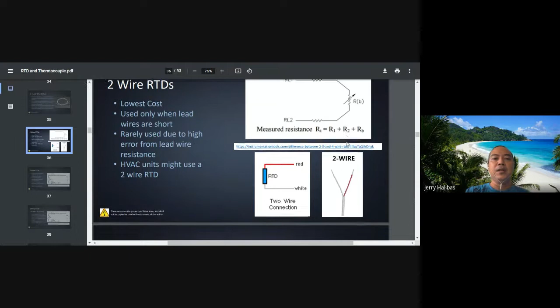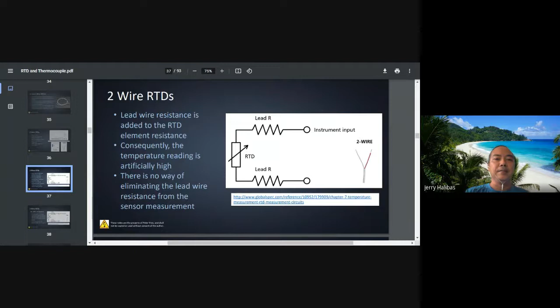Your reading will change. That's why you can still represent the circuit this way. So your lead wires or extension wire or instrumentation wire has an effect. Usually you use instrumentation wire because it's a braided type, similar to UTP or STP, shielded twisted pair, with braided shielding, even foil, but it's stranded because it's meant to bend, not solid. Unlike other twisted pairs which are solid, this one is several stranded wires.